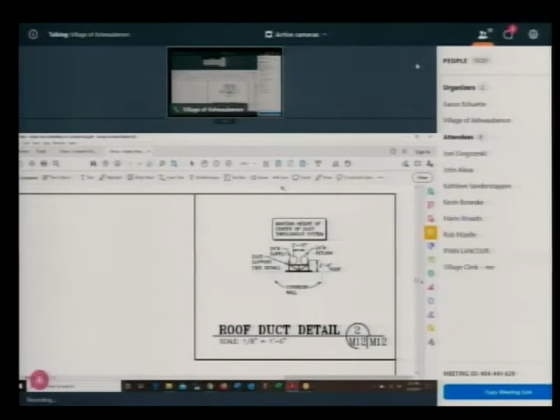The duct sizes vary, obviously bigger as you get closer to the HVAC unit located inside the building. The ductwork pops up on the building, gets supplied, and drops down into each individual classroom. The reason the ductwork is up on top of the school is these schools were originally designed with what you call unit ventilators—almost like when you go into a hotel, you've got your own personal unit on each wall. So when they designed this building, they didn't design the floor-to-ceiling structure height with adequate space to run duct mains inside the building.